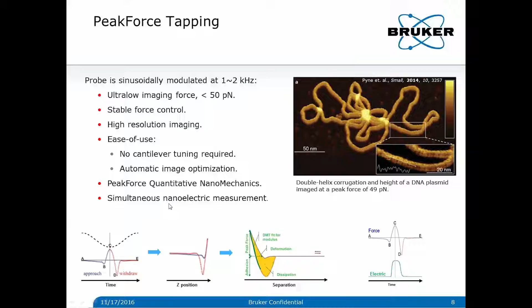Another feature of peak force tapping is that, because it is doing low-frequency tapping, each tapping cycle has a contact duration. For example, here from the snap contact to the break contact, from B to D, it has a duration of about 100 microseconds. So this is a magic. This is really a nice duration because it doesn't require very fast electronics. For example, if you have a sensor circuit that has 10 to 20 kilohertz bandwidth, then you can effectively capture any electrical signal during the tip-sample contact in this duration. So it also provides a simultaneous nanoelectric measurement.